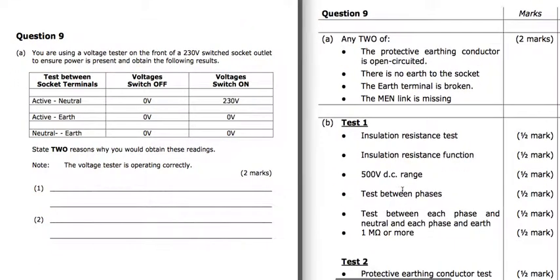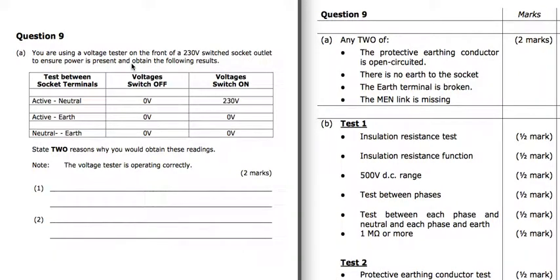Question 9, we've seen this one before, testing a voltage in front of a switch socket outlet. So we've gone, the switch is off, so that's what we would expect. With the switch on, active to neutral, we'd expect 230 volts, but active to earth, we would expect 230 volts there, wouldn't we? Neutral to earth is okay, 0 volts. So why are we getting these readings? So we've either lost the protective earthing conductor, it's gone open circuit, there's no earth to the socket, the earth terminal is broken, or the MEN link is missing.